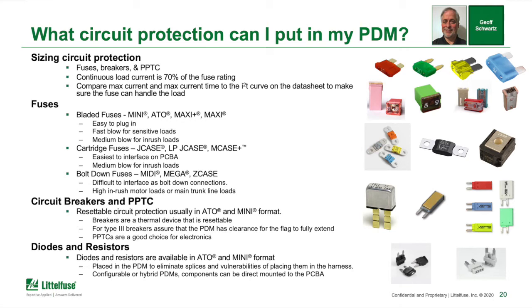Cartridge fuses are also readily available because they're used heavily in the automotive sector. So you can get either J case, LP J case, low profile J case, or M case available. Now, those are real easy to interface to the PCBA because they just use a blade terminal, and they're medium for inrush loads. Bolt down fuses, a lot harder to interface to a circuit board or any kind of PDM, simply because you have to find a transition from your bolt down to your PCBA or bus bar. But they're really good for high inrush motor loads or main trunk line loads.